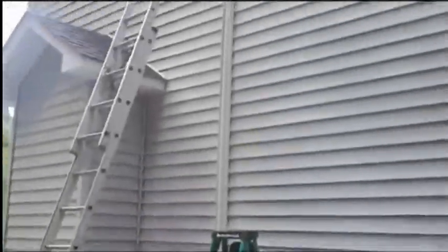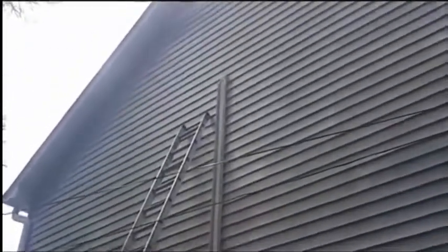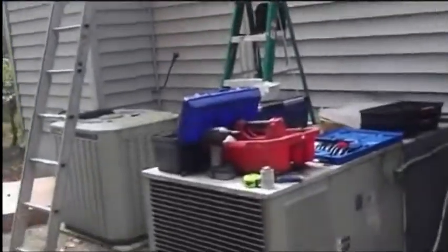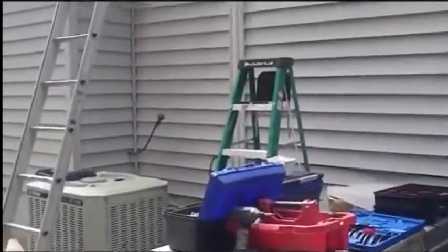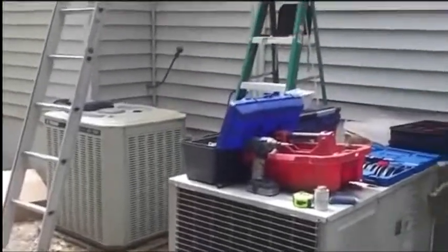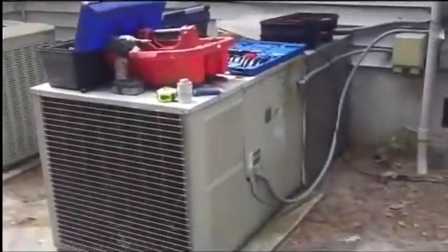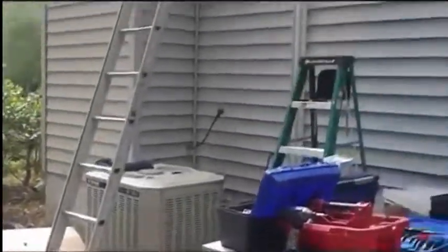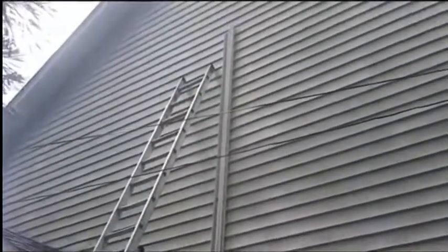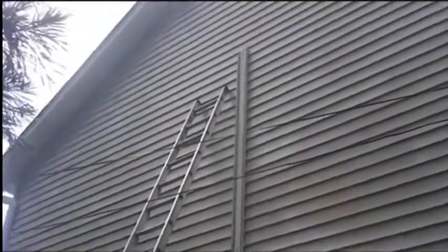Alright, today we're working outside on the line set. I got my channel up to run the line set down. I got my two drains in there, secondary and primary, one for the pan, one for the coil. I'm also going to add two float switches too, so it'll be well protected against water. So basically I'm just working the ladder in between my two little cables there, which are not high voltage. So that's where we're at.